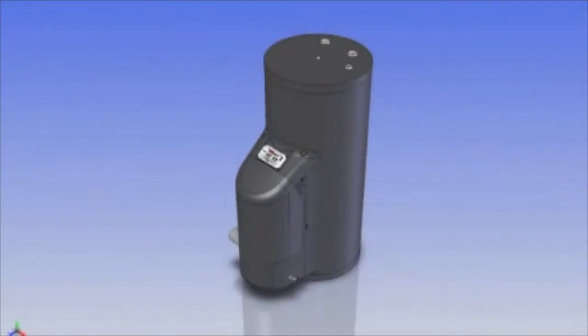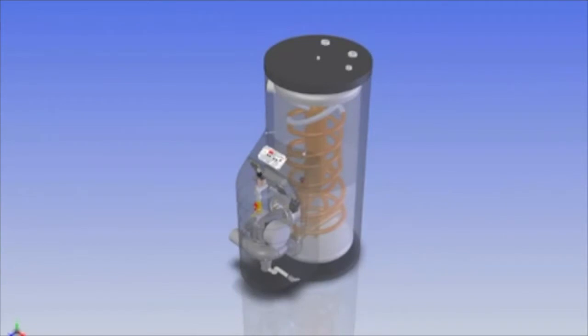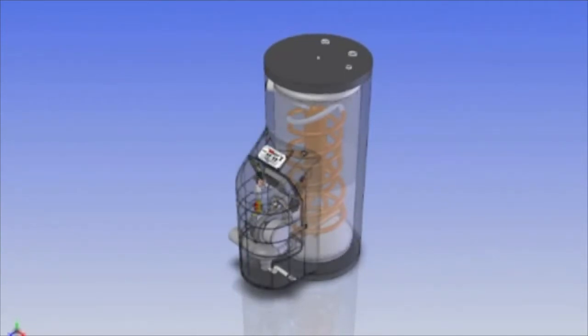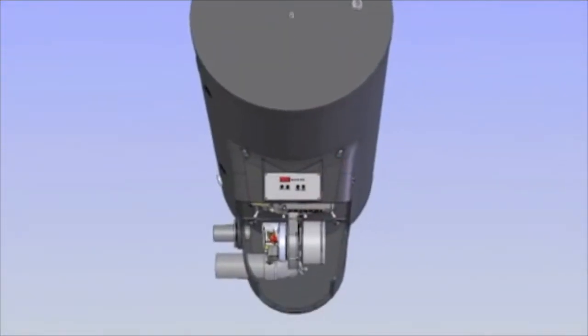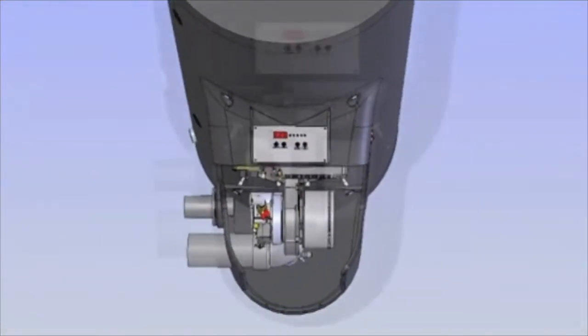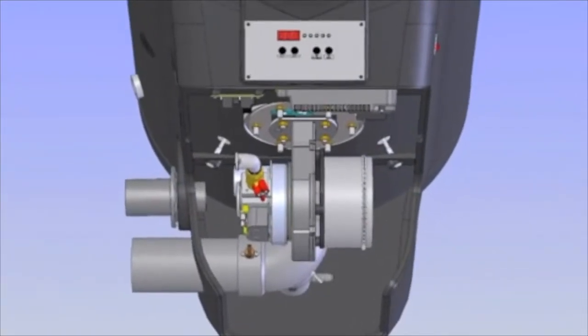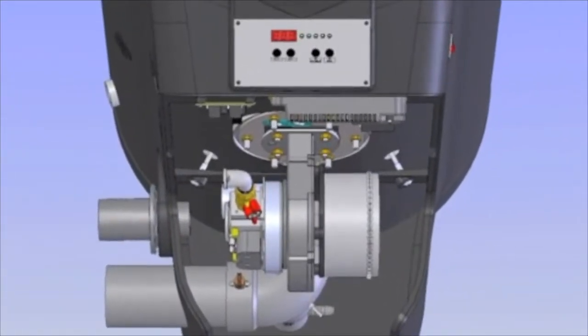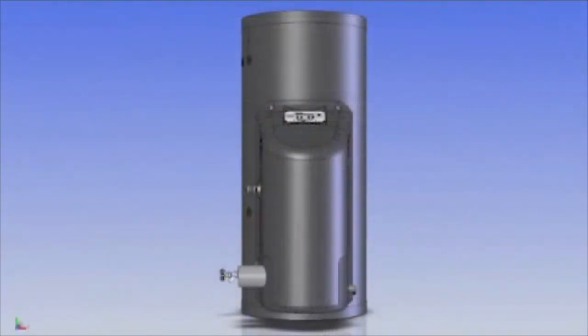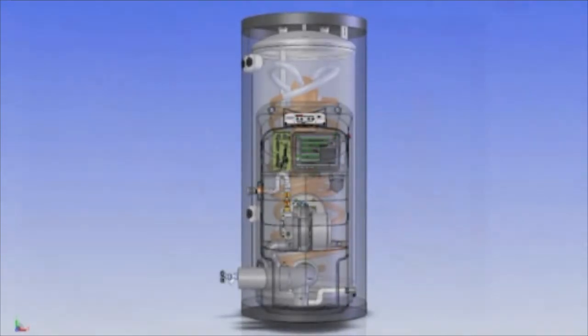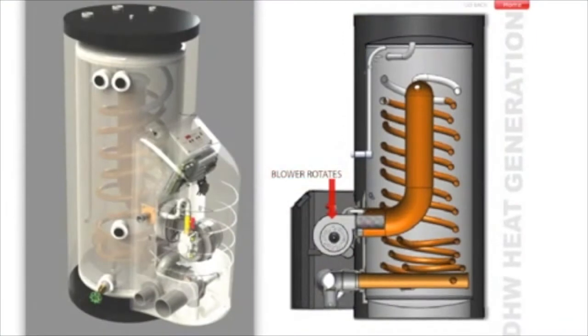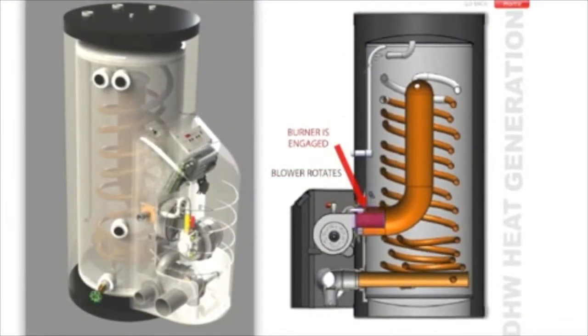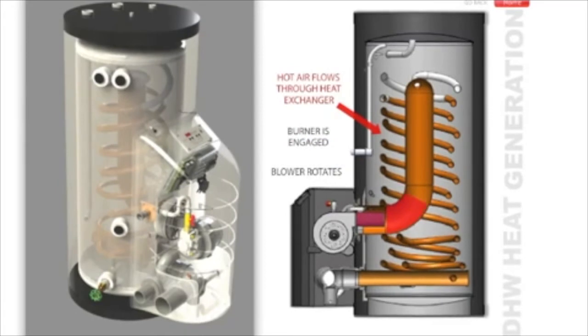Pioneer condensing technology maximizes efficiency by measuring the needs of your heating system through the use of sensors and a control unit. The heater uses data gathered by these sensors to intelligently deliver highly efficient hydronic heating. The Pioneer's internal PI controller continuously monitors system conditions and modulates the combustion air fan speed to meet demand. Negative regulation technology induces just the right amount of gas through the valve to mix with the fresh air intake. This ensures the most efficient combustion across the burner.